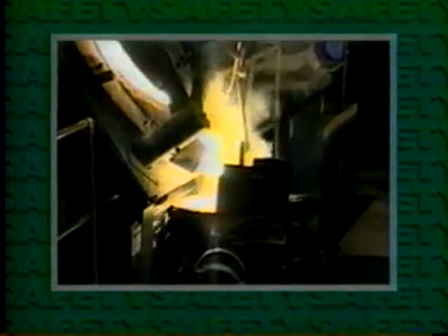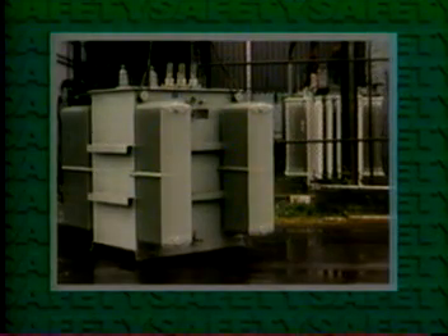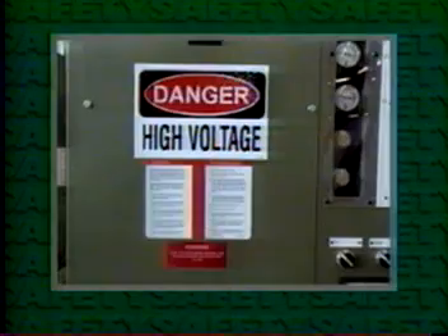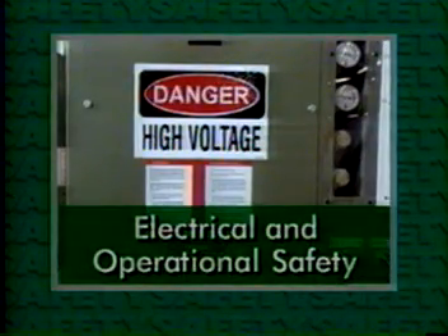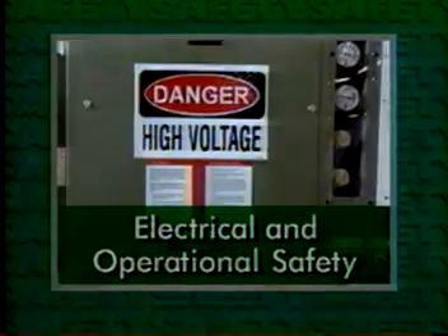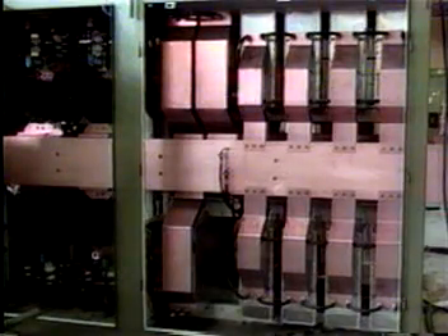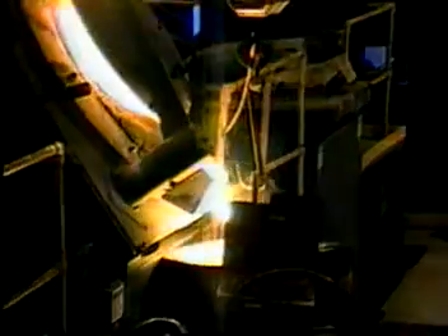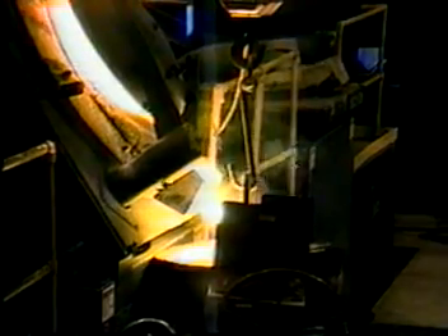While many electrical systems in foundries are similar to those in other industries, a foundry's induction melting system involves high levels of electrical power, levels more commonly associated with power company substations. For this reason, induction systems require special attention to electrical safety. Induction systems with their open-air bus bars and other exposed conductive surfaces present more electrical hazards than most other types of industrial equipment. Consequently, modern induction furnaces and power supplies are designed with safety systems to reduce these hazards.